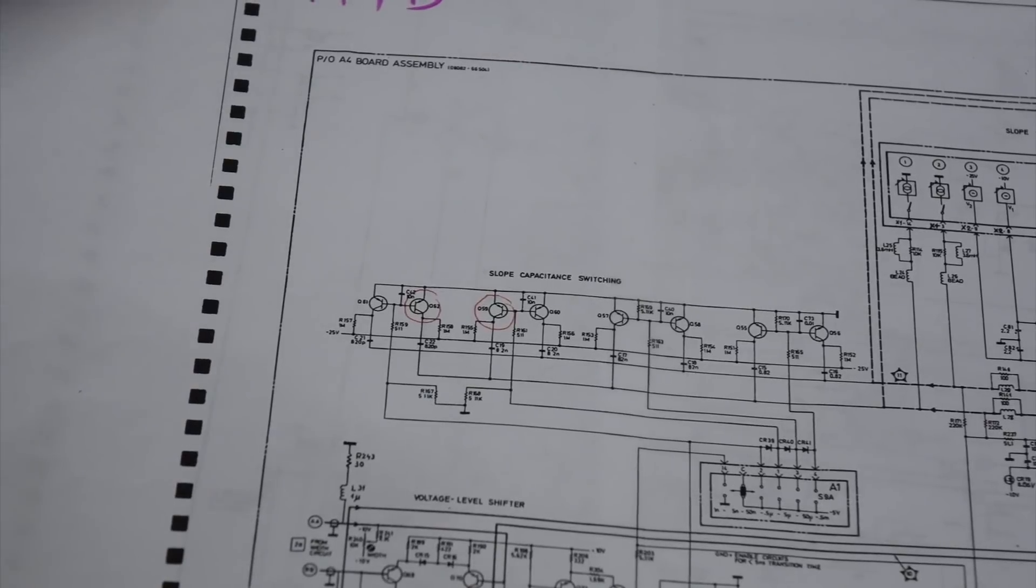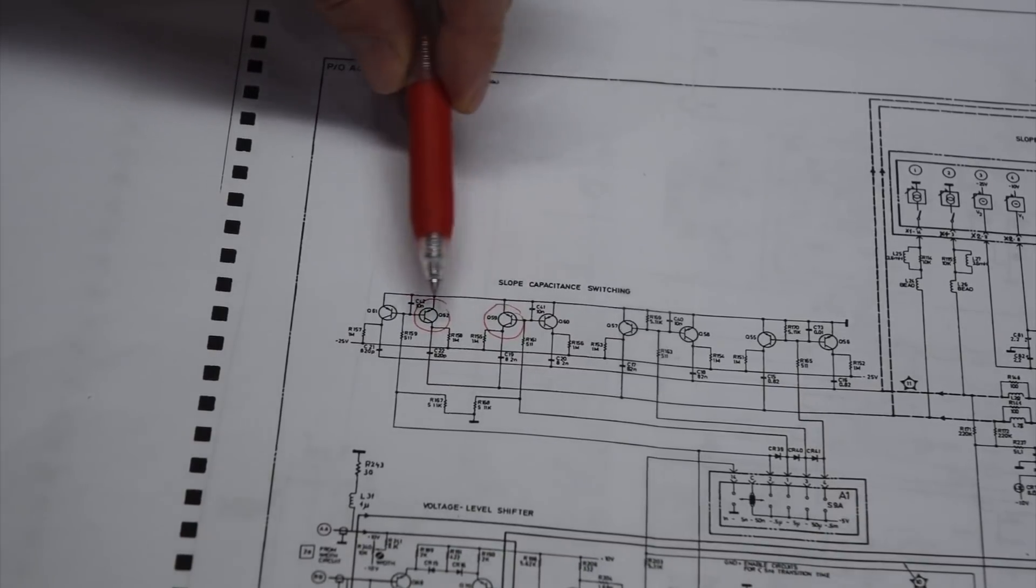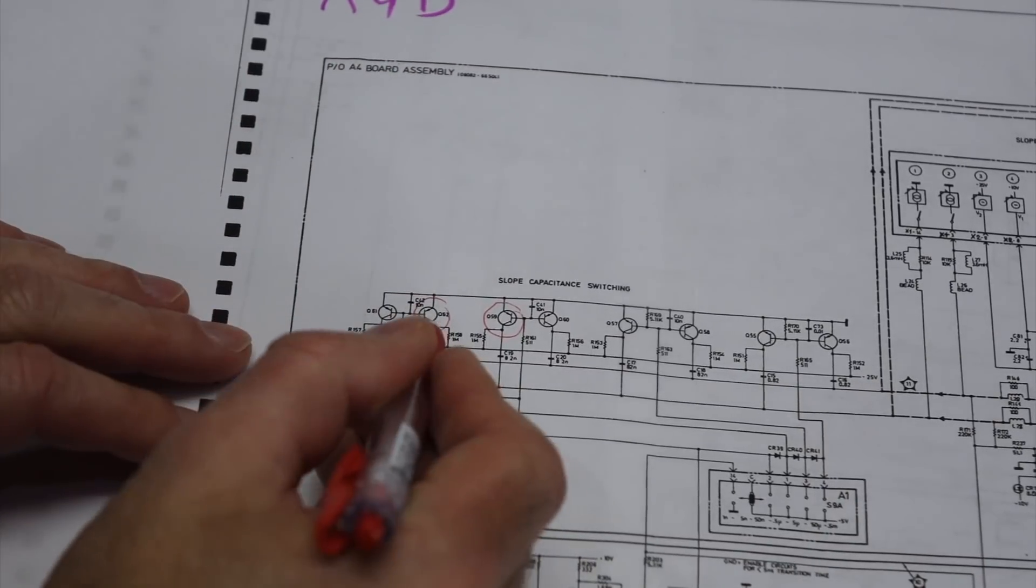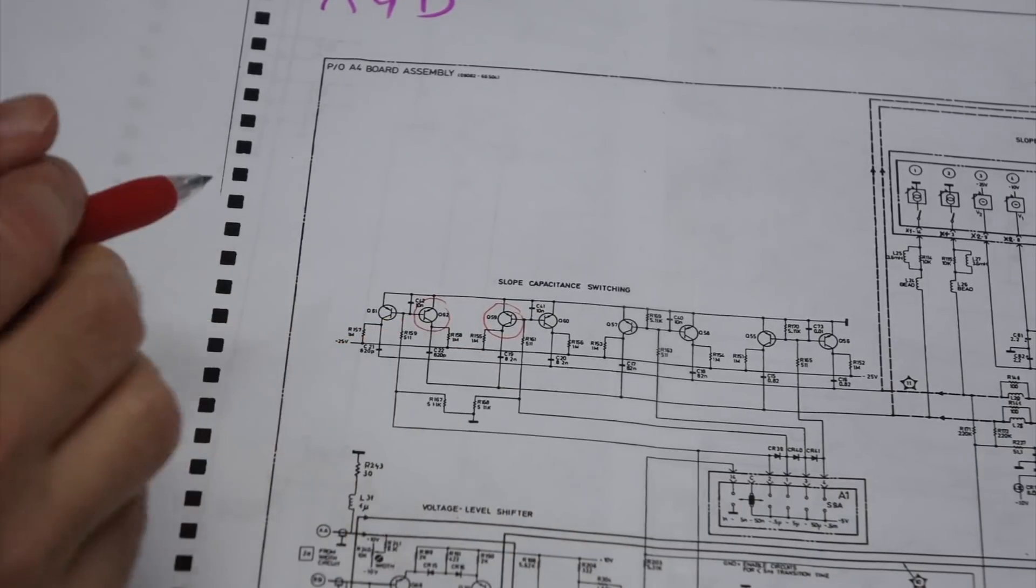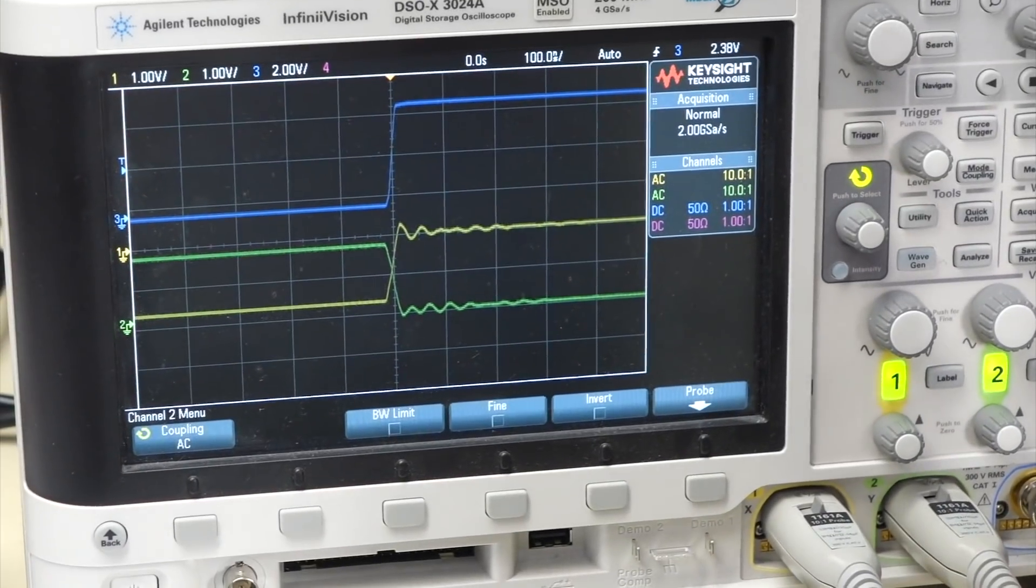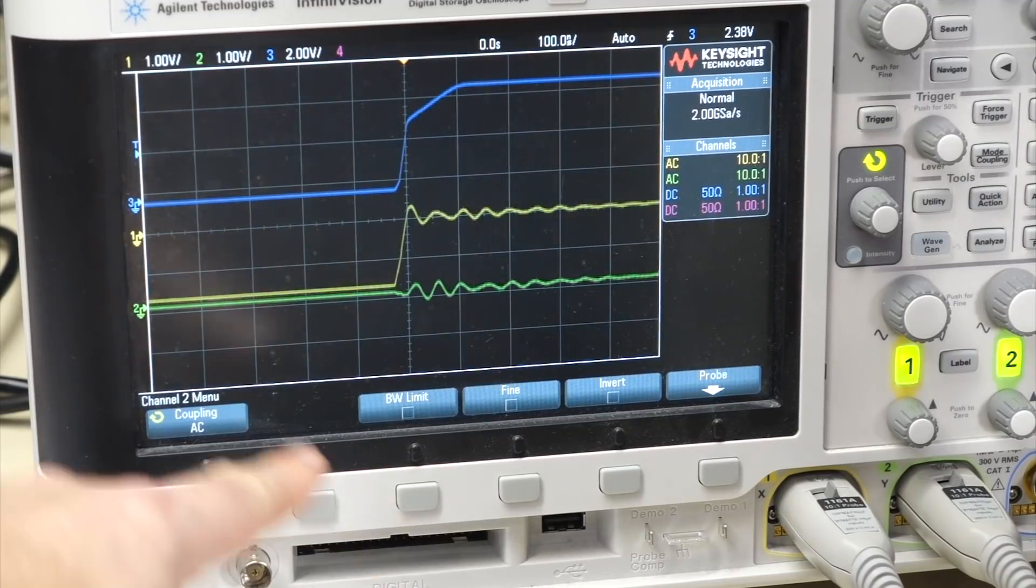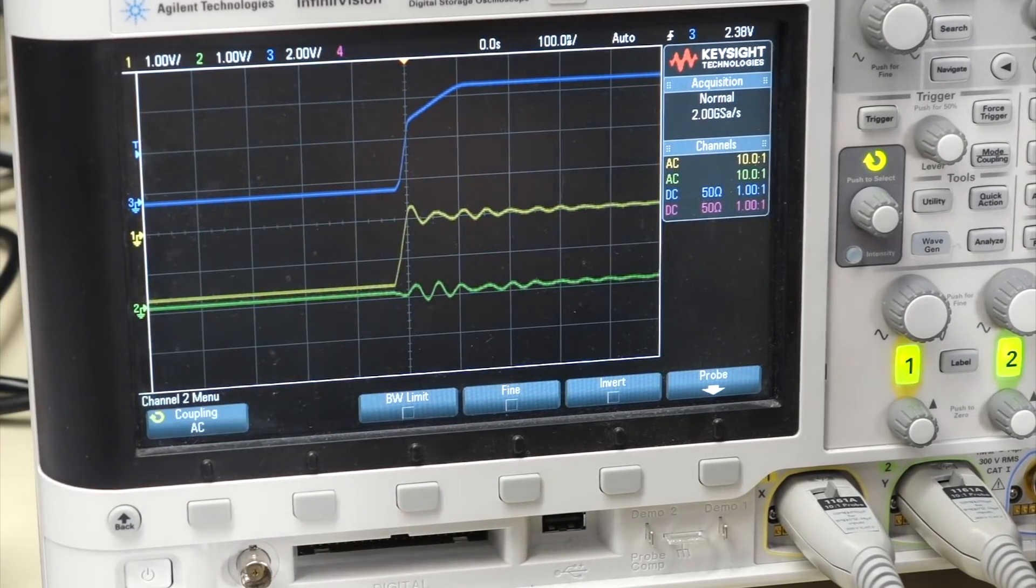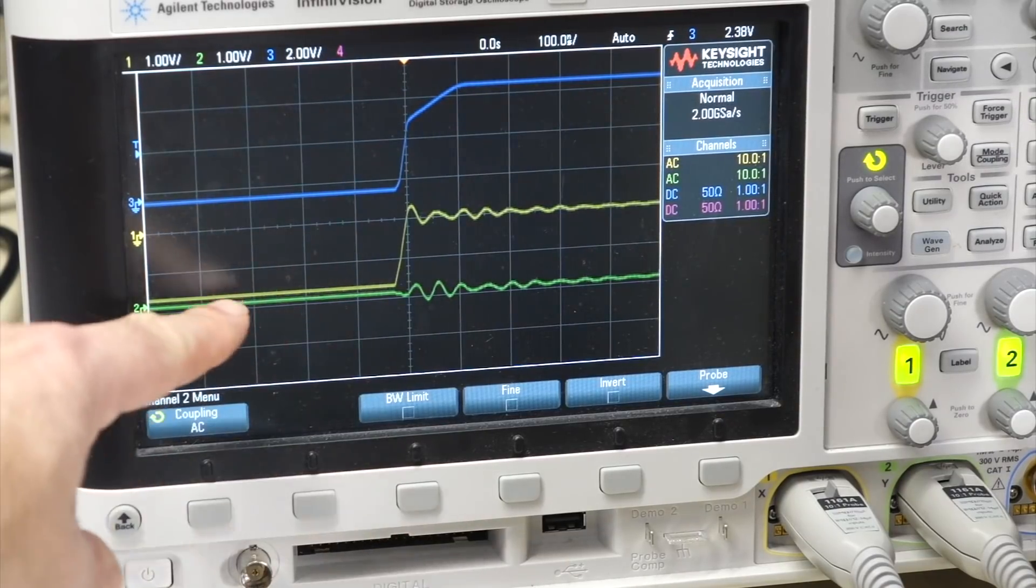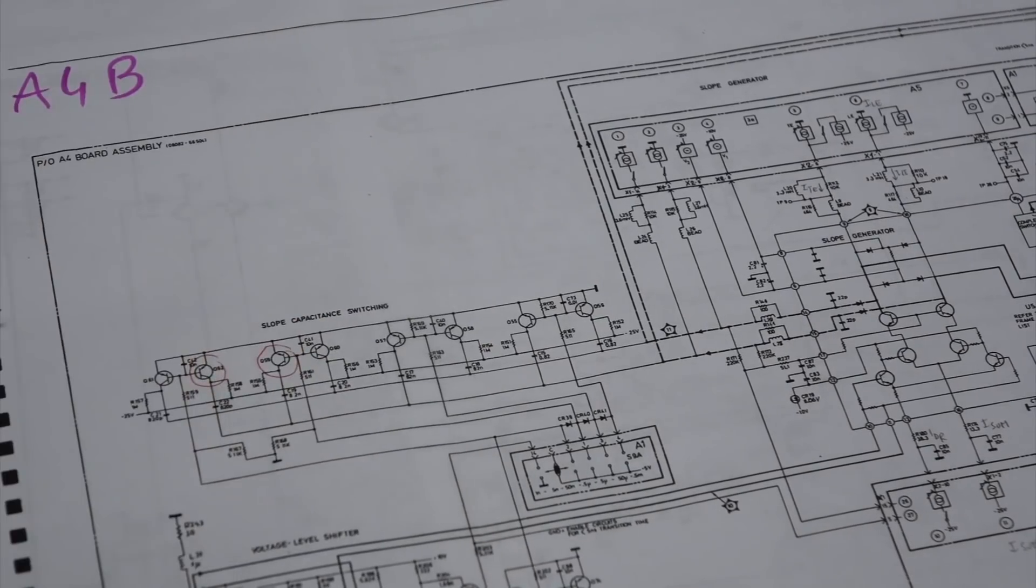I found the two transistors that don't work. It's Q62 and Q59. So I'm on this pair right now, so I'm looking at something that should be symmetrical on both of those. And so right now they are not selected. And then I go to the range where it should be selected, and you see only the green one gets selected. The yellow should have been grounded. The one that's attached to the yellow transistor is the faulty one.